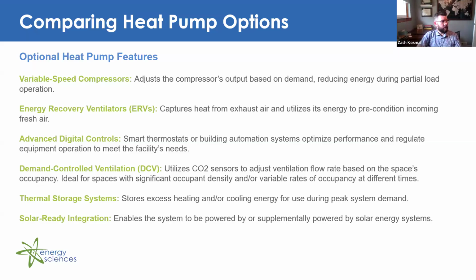You also have DCV or demand controlled ventilation. These options typically utilize CO2 sensors to adjust ventilation flow rate based on a space's occupancy. So these are ideal for spaces with significant occupant density or significant variance in rates of occupancy at different times. We also have thermal storage systems, which store excess heating or cooling energy for use during peak system demand. And you have solar ready integration, which just enables the system to utilize solar panels for supplemental power or full power. So one example of a thermal storage system application, maybe a facility that has a demand charge or time of day rates based on their bill to shift off during peak load hours. Perfect situation for a thermal storage system, which could help alleviate those additional charges when those thermal storage systems are utilized properly.